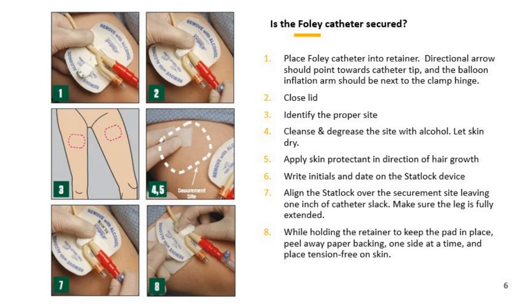The abdomen is recommended for chronic Foley use in bedridden male patients to prevent the downward pressure that often leads to meatal erosion. Place the StatLock Foley stabilization device on the right or left side of the abdomen with the same 1 inch of slack. Once the site is identified, gently place the StatLock Foley stabilization device off to the side. Cleanse and degrease the stabilization site using 3 to 4 alcohol pads to remove oils, lotions and secretions from the skin. Remember to cover an area much larger than the actual targeted stabilization site. Allow alcohol to dry completely.